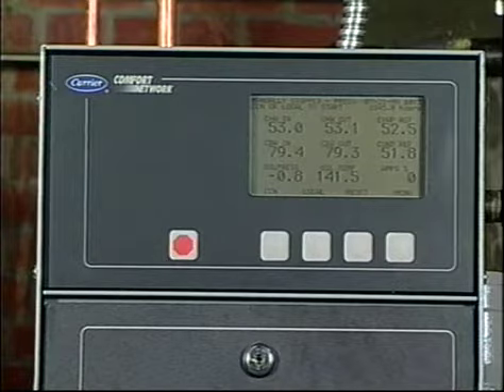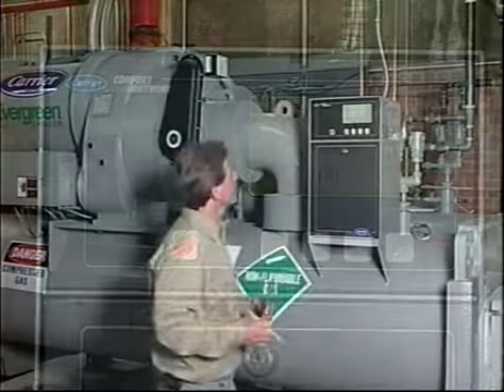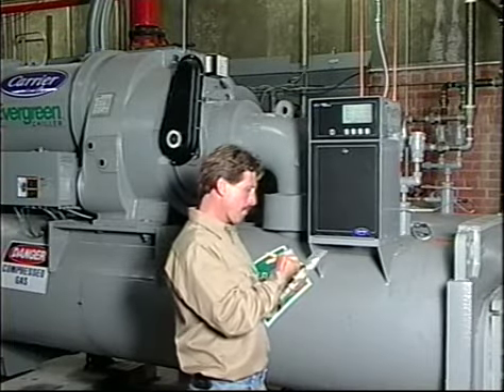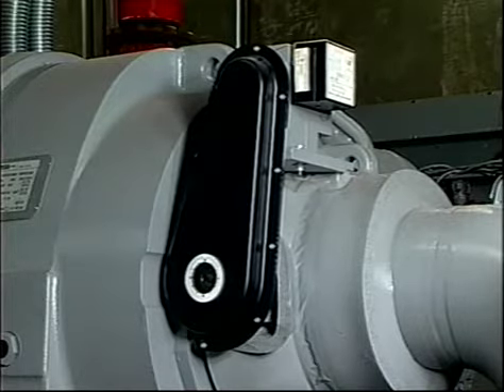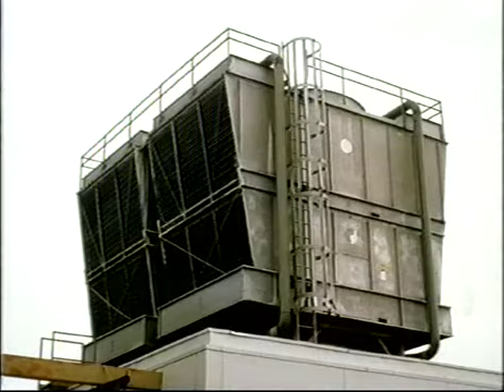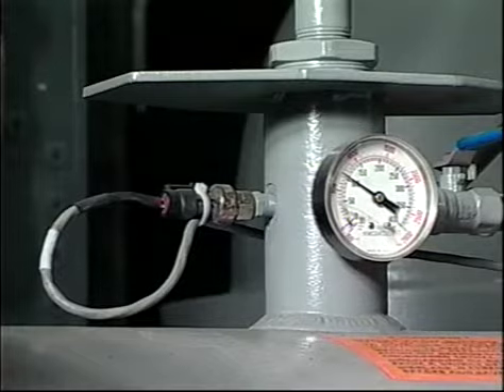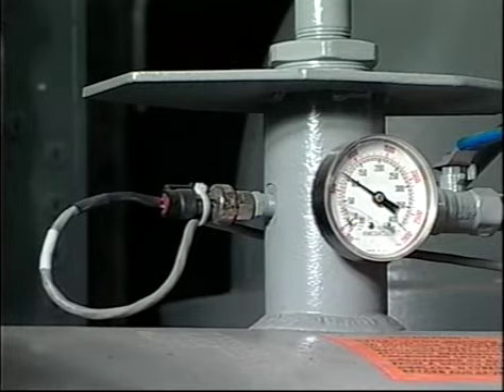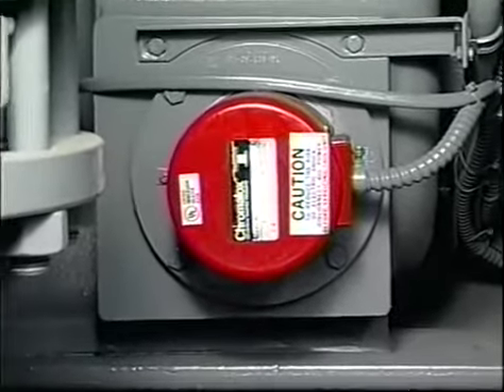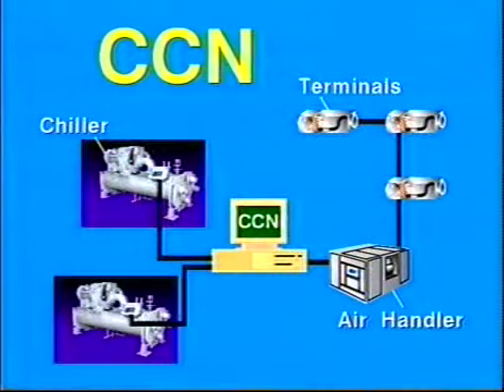The PIC controls the operation of the chiller by monitoring all operating conditions. The PIC can diagnose a problem and let the operator know what the problem is and what to check. It promptly positions the guide vanes to maintain leaving chilled water temperature. It can interface with auxiliary equipment such as pumps and cooling tower fans to turn them on or off when required. It continually checks all the safeties to prevent any unsafe operating condition. It also regulates the oil heater while the compressor is off. The PIC can interface with the Carrier Comfort Network, or CCN, if desired. It can communicate with other PIC-equipped chillers and other CCN devices.